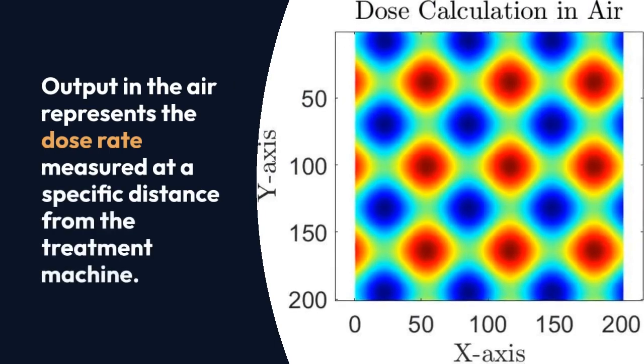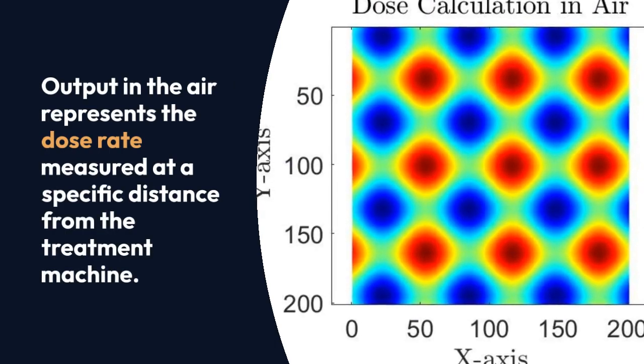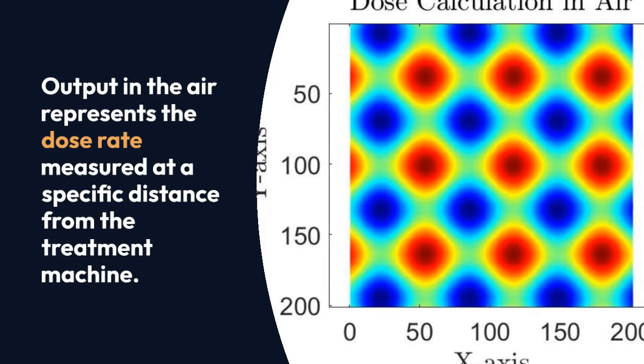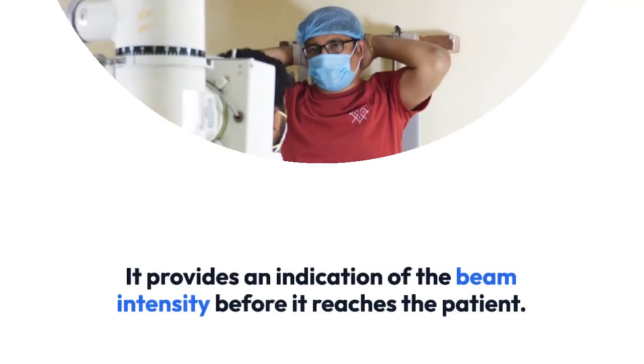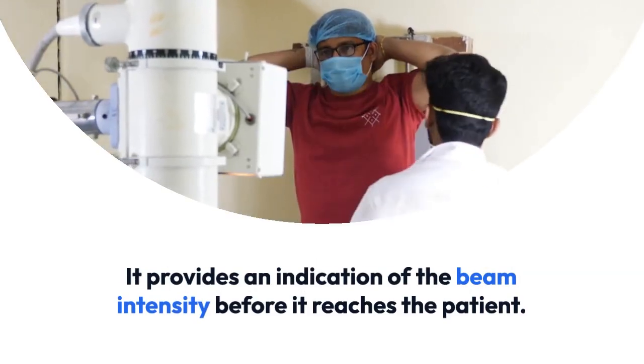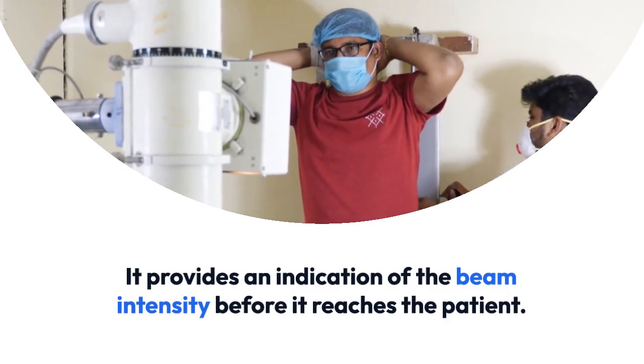Output in the air represents the dose rate measured at a specific distance from the treatment machine. It provides an indication of the beam intensity before it reaches the patient.